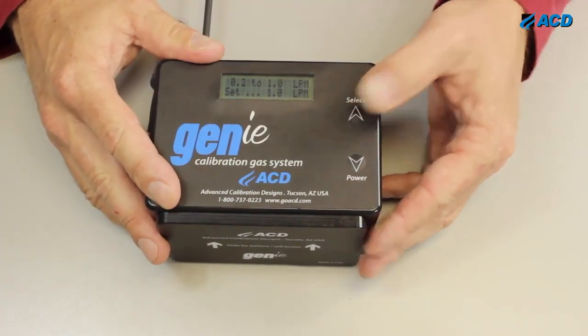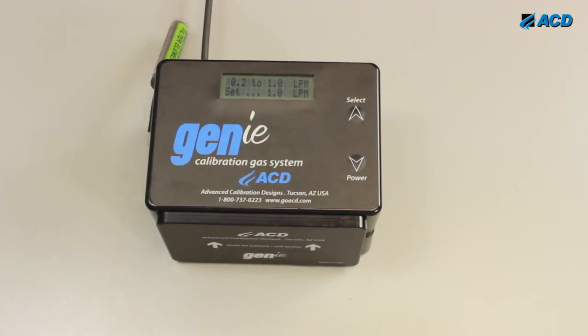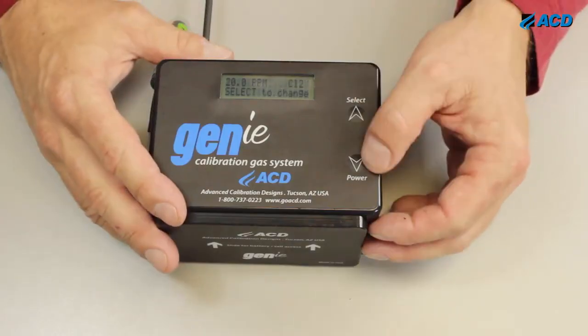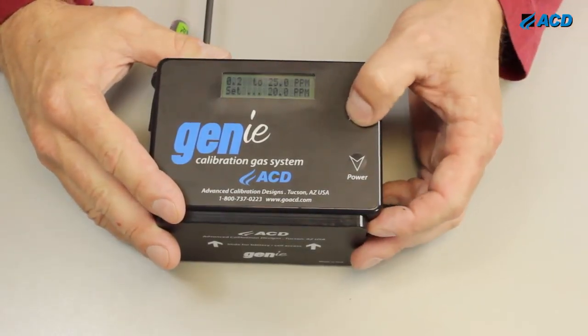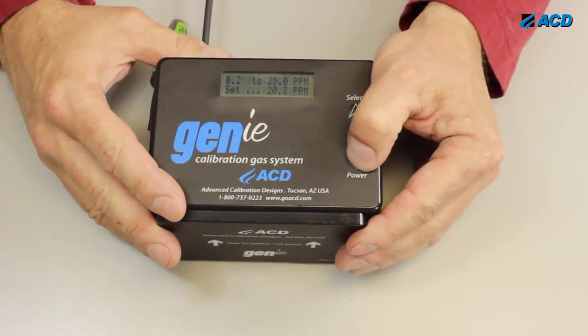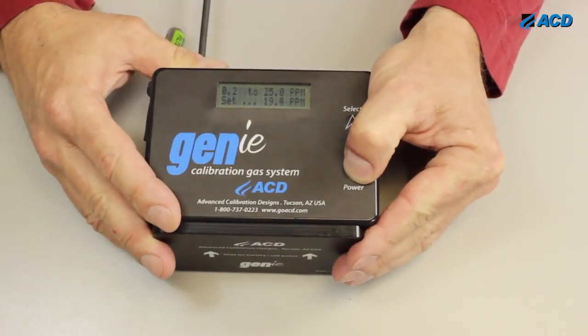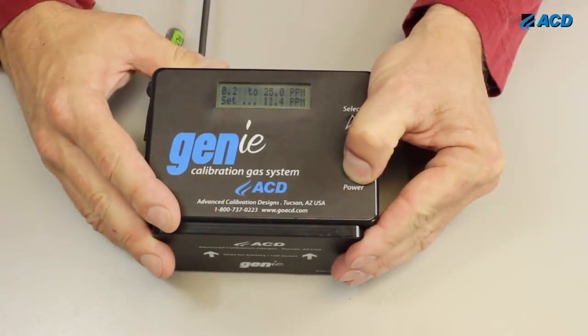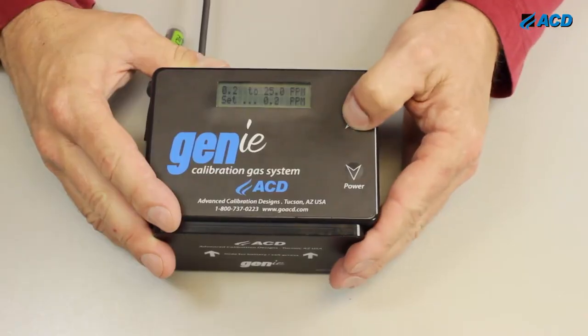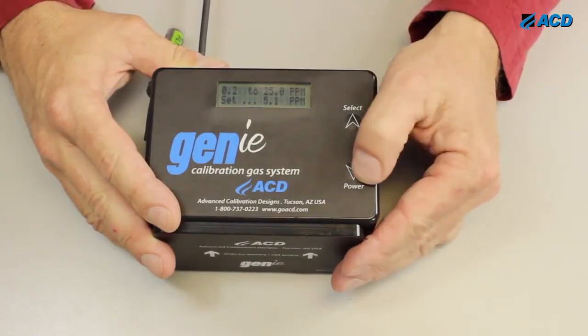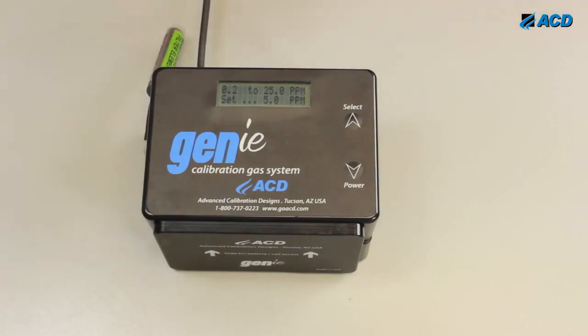I'm going to change the flow just to show you to 1 liter per minute. Maybe this brand wants 1 liter per minute flow. And then it's showing 20 parts per million. I'm going to assume for this example that this brand wants 5 ppm. So I go to 5 parts per million. Now I've changed the flow rate and the concentration, so the unit has to restabilize, okay?